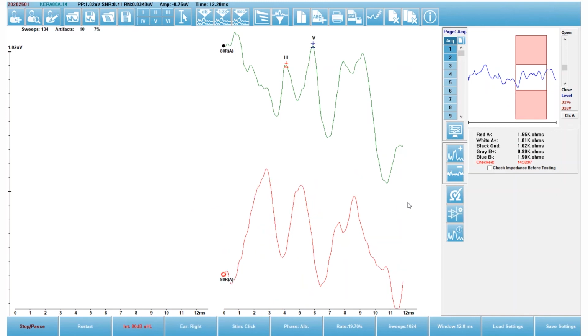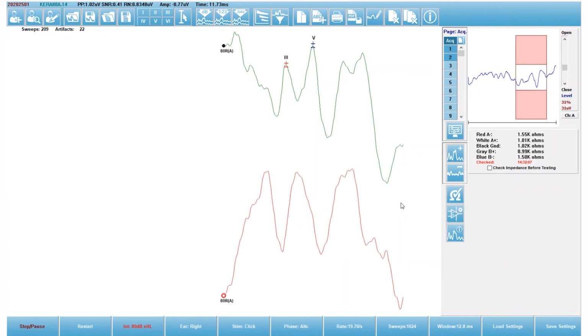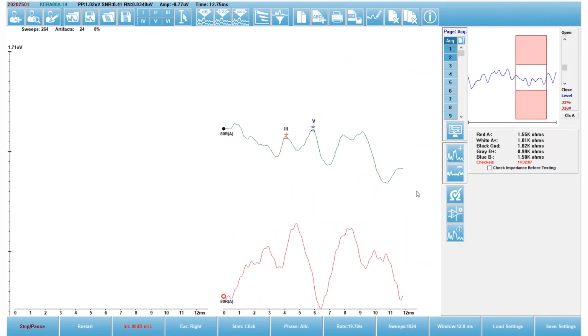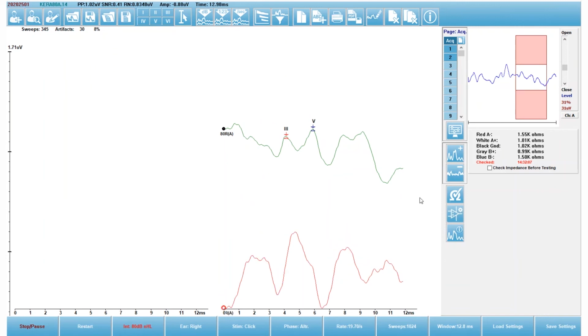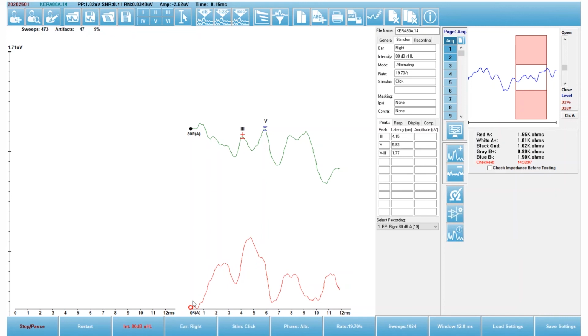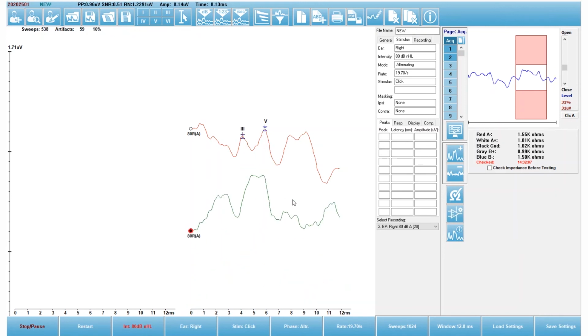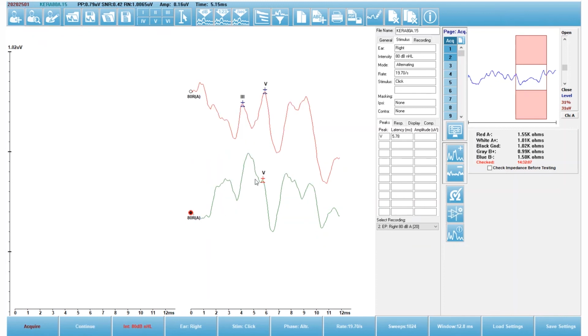Again, the sweeps in the upper left-hand corner of the screen, as well as number of artifacts. Increase and decrease the waveform size during collection. Recording information for each waveform, and that's for the waveform that is the active one, which would be in green. So the second waveform is still collecting. I haven't marked anything, so that's going to be blank. If I select the other waveform, I have 3 and 5 marked, so I'm able to see my latencies. I'm going to go ahead and select that second waveform, mark wave 5. It's a little bit different than the other waveform, etc.